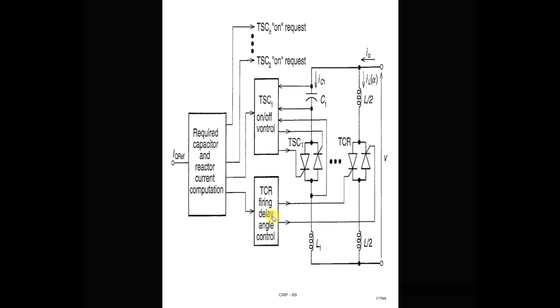So again to repeat, IQ reference is the actual amount of reactive current required to maintain the voltage. Based on that, from each TSC branch current, it calculates the total number of TSC branches required to connect, and after that, based on the excess reactive power capacity, the TCR control scheme generates the firing angle delay to absorb the excess reactive power from the system.